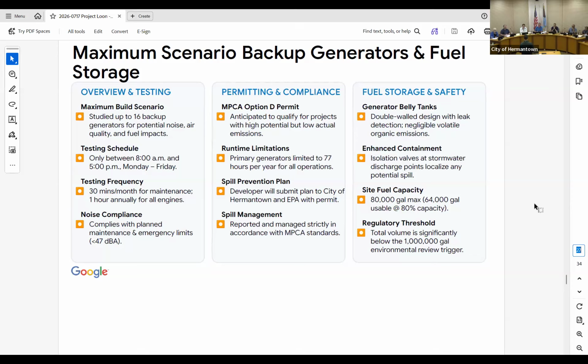As far as permitting of the backup generators, the project is anticipated to qualify for what's deemed an Option D permit with the MPCA, which generally covers projects that may have a high potential for emissions but actually low emissions, based on being used for backup generation purposes only. To comply with that permit, those generators would be limited to at most 77 hours per year for all operations, inclusive of any grid outages. They would need to remain compliant with that.